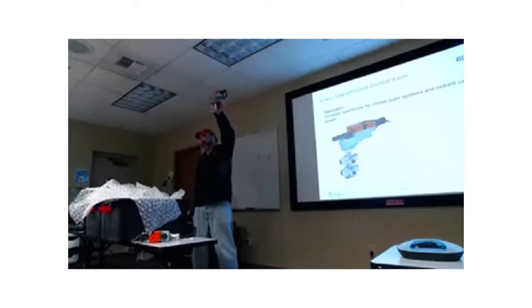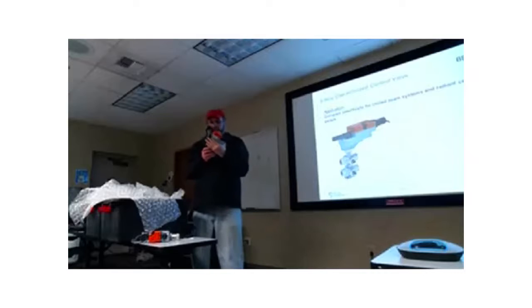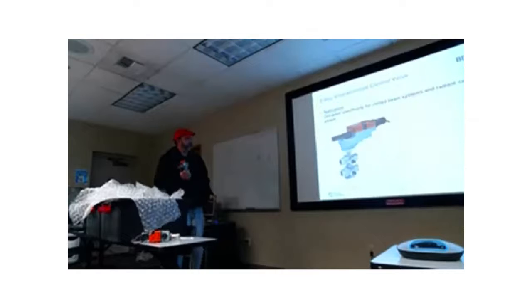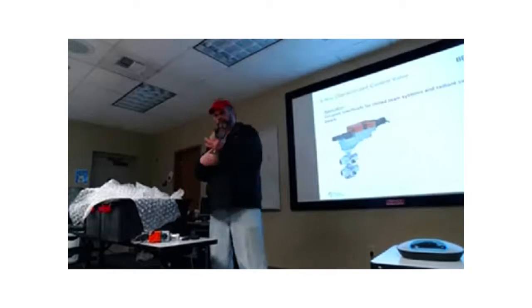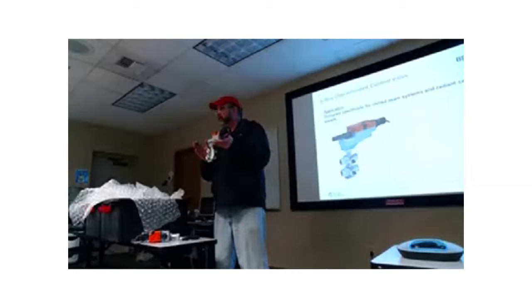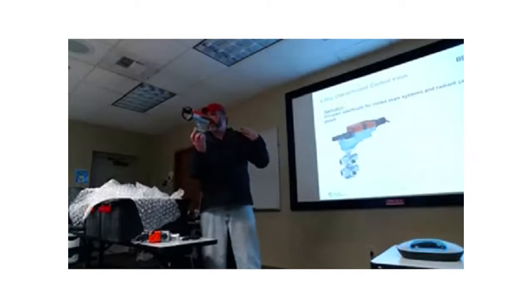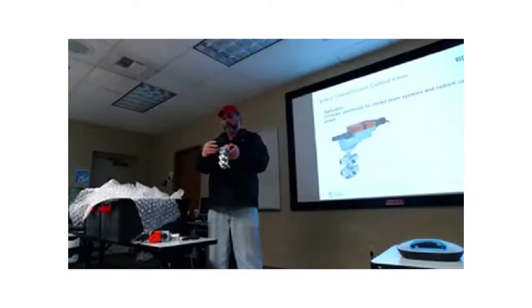6-way valve. So here it is, right? You've seen one in the flesh. Now we only make these in non-spring return actuation, but just so you can say you've seen one, I'm going to pass it around. Let me show you how it works. It's only got a 90-degree stroke, 90 degrees total. You start out with the heating side: 30 degrees stroke for the heating, 30 degrees deadband, and then 30 degrees for the cooling. So with one control signal, you can control both the heating and cooling to the coil, and like I say, you get away with just one control connection. So it's a potential labor saving device.